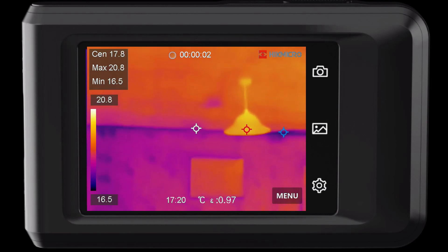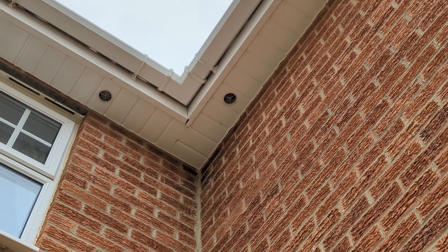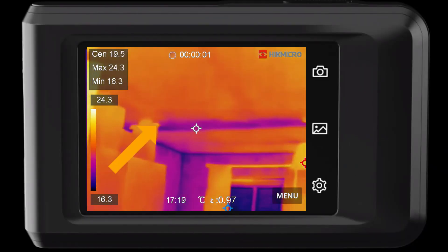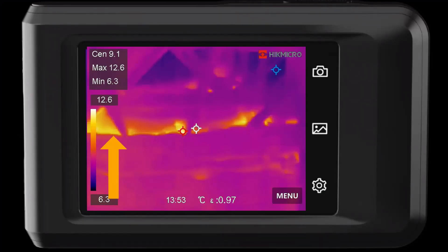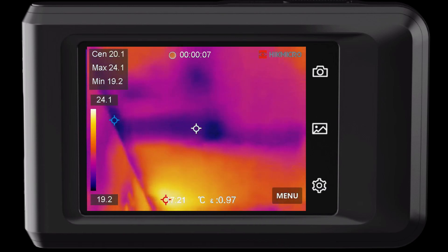Using the Pocket 2, let's see how our loft insulation is doing at keeping the heat in our living space. You can see in these bedrooms there is a consistent pattern of infiltration at the edges of the ceiling from the external walls and therefore heat loss. This is most likely coming from cold air moving through the soffit ventilation into the loft space, but this is important to avoid condensation and mould build-up, so I suspect this area of heat loss may be unavoidable. The Pocket 2 also identified other cold surface areas in the main ceiling area itself — this linear blue and colder area seen here represents a joist creating a thermal bridge, where heat is allowed to escape through the joist, creating a bridge between the warm ceiling and cold roof space. The thermal camera also picked up a similar issue in our bathroom, which explains why we sometimes get condensation forming in that one particular place in winter when warm humid air comes into contact with this thermal bridge.